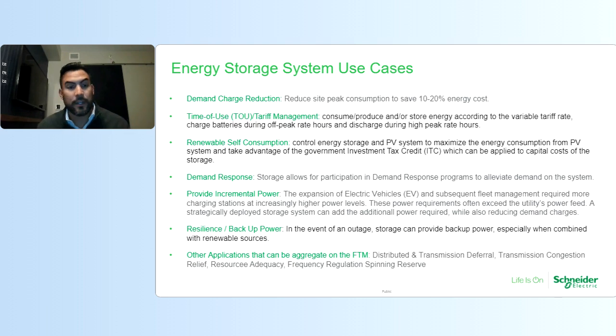Self-consumption, right? Depending on the geographic region, a few years ago it was beneficial, where you can export back to the grid. Now, believe it or not, if you have these on-site generating assets, whether it's PV and/or an energy storage system, it's actually cheaper to produce power on-site and consume it for your facility rather than purchase it from the utility at certain hours. Demand response: participate in a utility program to help with frequency regulation, incremental power, right? If you don't get the approval rating from the utility for an expansion, an energy storage system can help suffice that incremental power that your facility needs for operation.